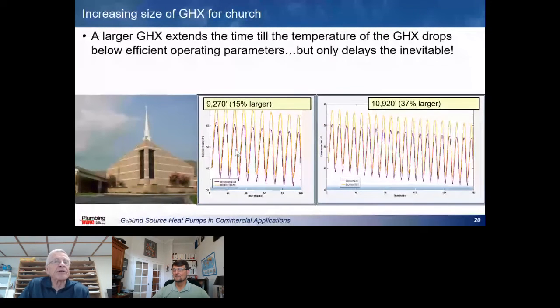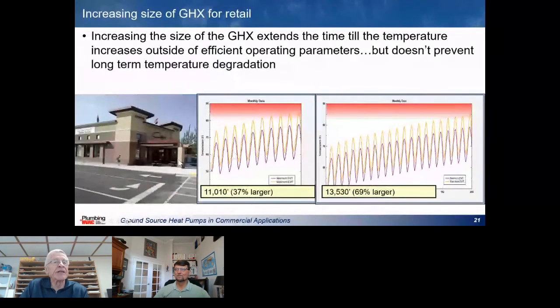Installing more pipe in the ground is all that's going to do is delay the inevitable, in this case, cooling of the ground. Even though you've got a larger ground loop, it's going to take a little bit longer to cool off too much. Even if you're looking at 11,000 feet of drilling instead of 8,000, it's going to eventually get to the point where it's too cold. Same thing in the retail store. Even if you increase the size from 8,000 up to 13,000 feet of drilling, this is eventually going to get too warm.